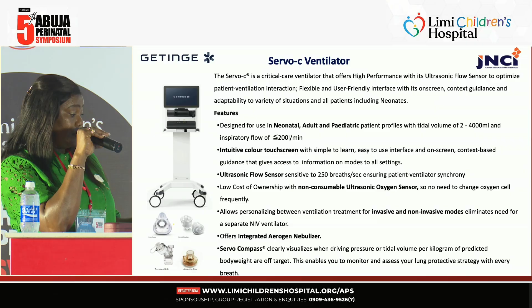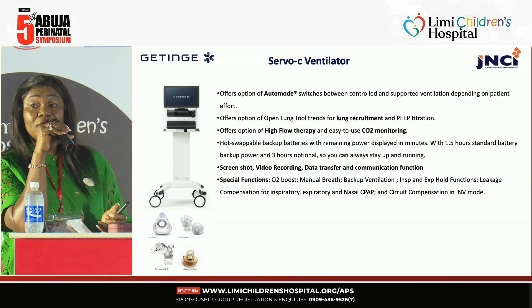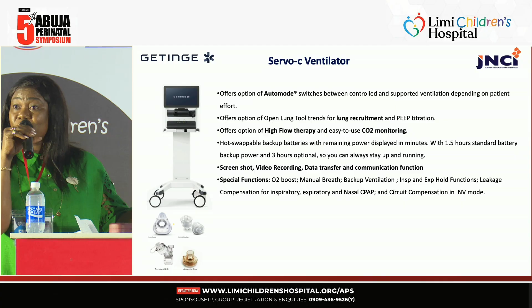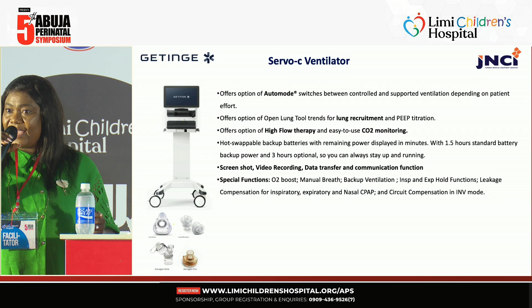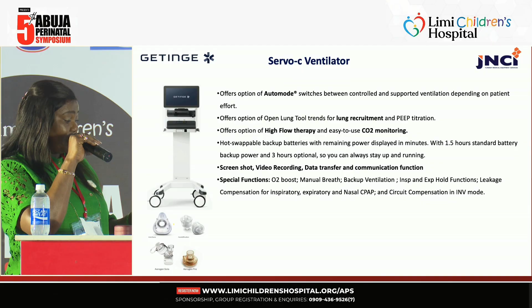Still moving on, we have what we call the auto mode, which is a mode that integrates based on the physiologic response of the neonate. So it helps the ventilator to automatically take over and begin to administer the breaths in a situation where the baby is not able to initiate a breath, and that is called the auto mode. And all of this I have also mentioned with the special functions.